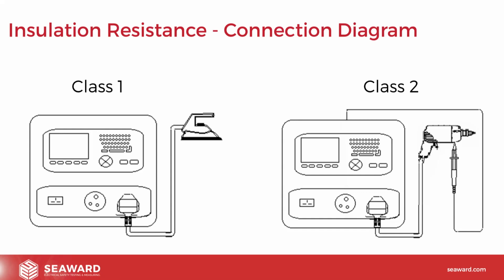With a class 2 product, as we all know, there's no earth cable. So with the lack of an earth cable, what we do is simply apply an external probe to exposed metalwork. And again, those points will be exactly the same points that you might use when performing the flash test. Any current flow is then picked up, flows back into the instrument, and the limit is judged according to what's flowing back.